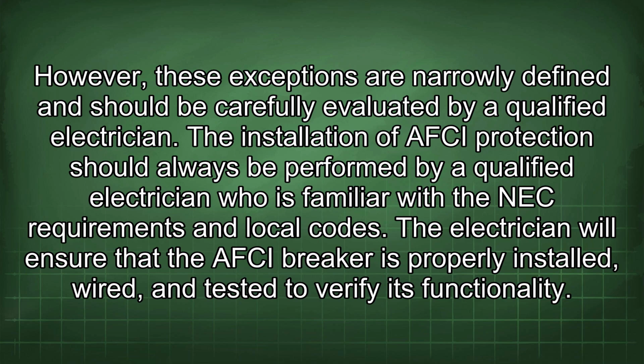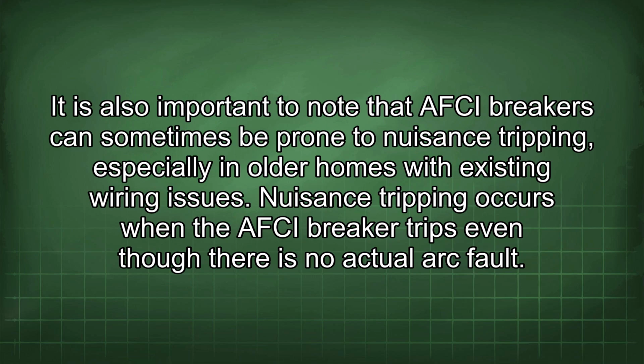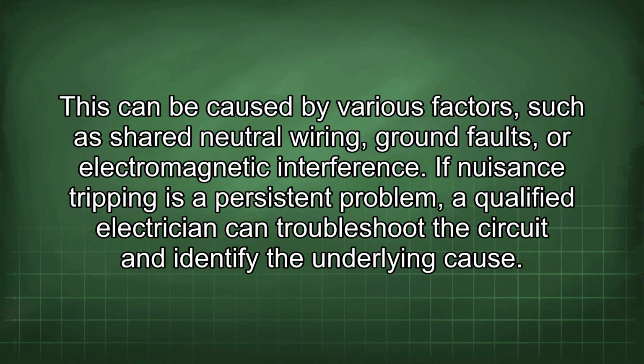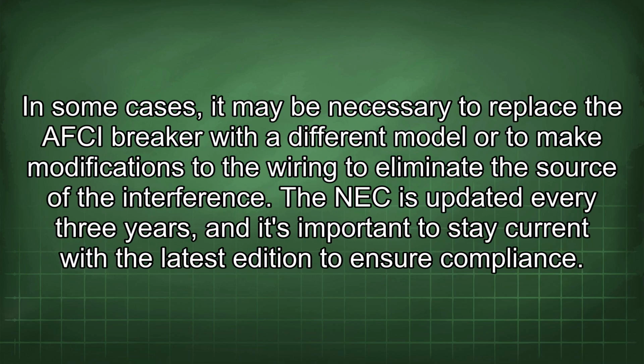The installation of AFCI protection should always be performed by a qualified electrician who is familiar with the NEC requirements and local codes. The electrician will ensure that the AFCI breaker is properly installed, wired, and tested to verify its functionality. It is also important to note that AFCI breakers can sometimes be prone to nuisance tripping, especially in older homes with existing wiring issues. Nuisance tripping occurs when the AFCI breaker trips even though there is no actual arc fault. This can be caused by various factors such as shared neutral wiring, ground faults, or electromagnetic interference. If nuisance tripping is a persistent problem, a qualified electrician can troubleshoot the circuit and identify the underlying cause. In some cases, it may be necessary to replace the AFCI breaker with a different model or to make modifications to the wiring to eliminate the source of the interference.